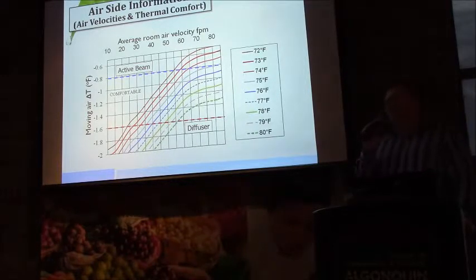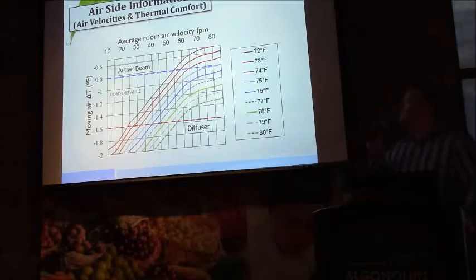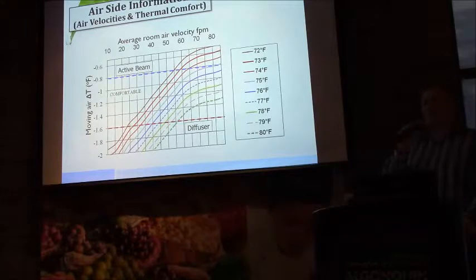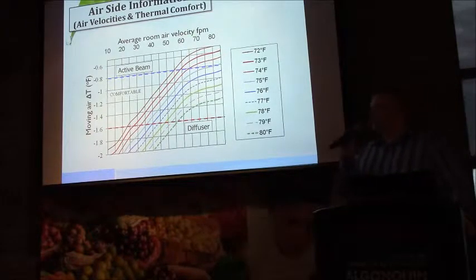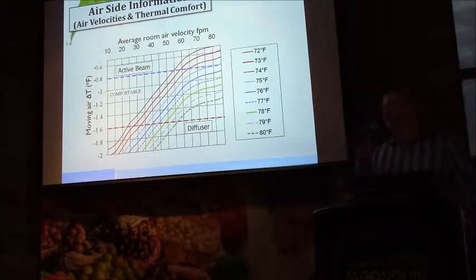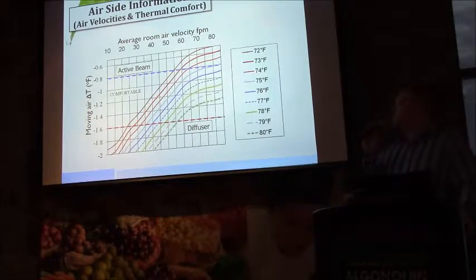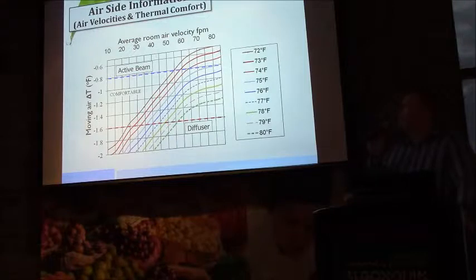Now, ASHRAE Standard 55 says that we cannot do this, but the concept is carried through such that there is less risk of draft to have a warmer airstream distributed in the space. And the high induction ratio, more correctly, that passes through the beam, the lower the risk there is, of course, of creating draft.